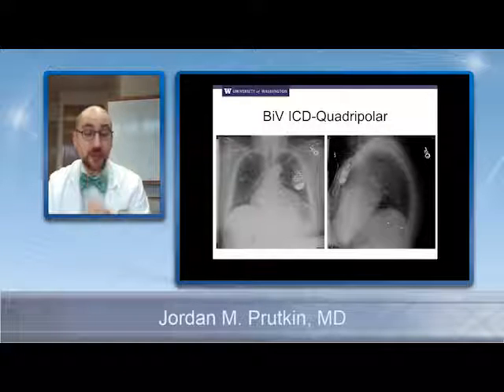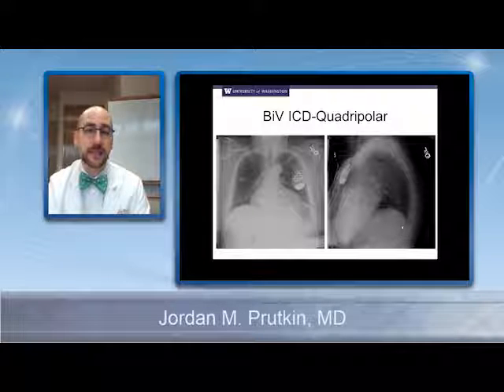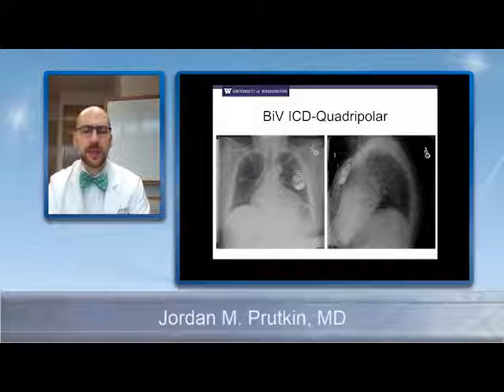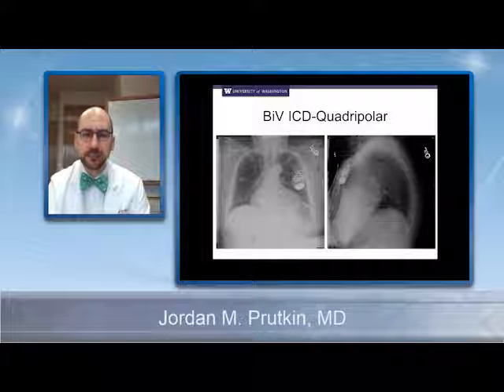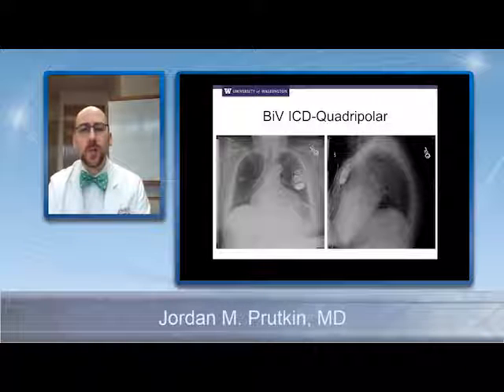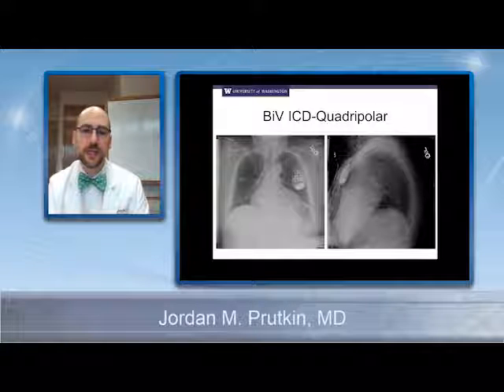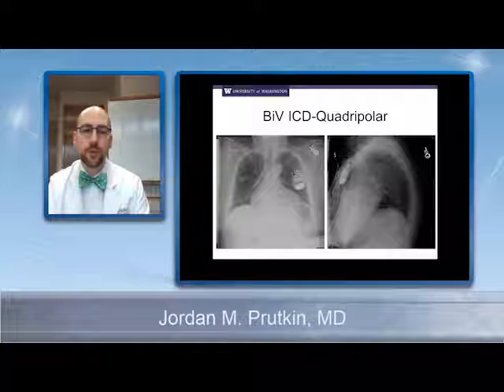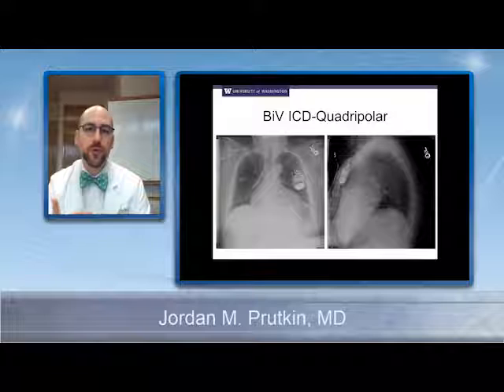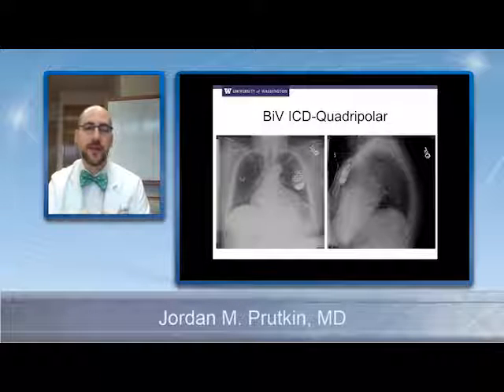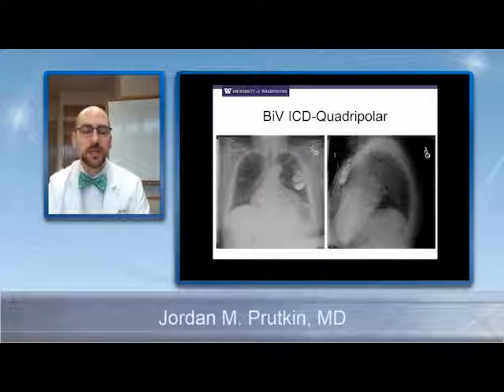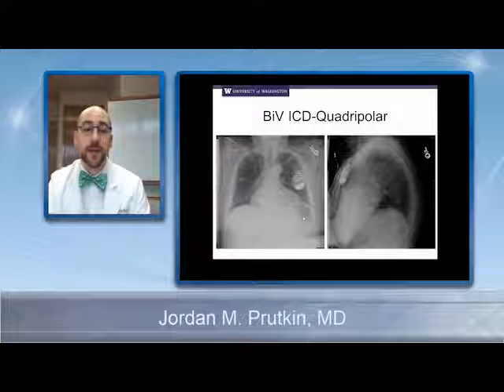So the benefit of these newer devices, or the newer leads, has to do with, in a lot of ways, reducing complications of the device. So number one, what you want to do, if you can, is try and pace the heart in as basal a location, as far backwards towards the mitral valve as you can. And with leads that only have 2 poles on them, if the lead goes in very far towards the apex, you don't have a pole far enough back to be able to pace the heart. And so this is a way to improve the success of the device, to be able to pace more in one of these basal locations.